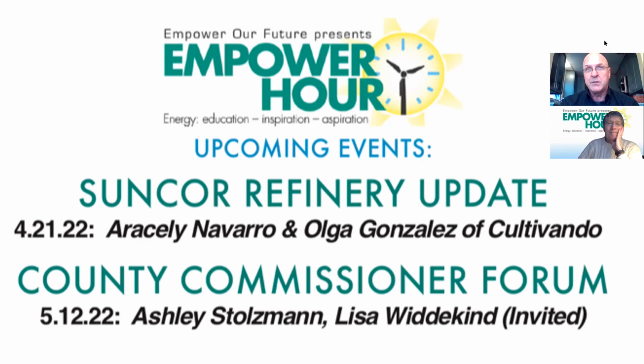They pull about 80% of the power out of their supercapacitors every day, doing peak shaving as the machines go off and on. And then at night, when everybody's gone home, they recharge those. They do mitigate it to some degree also with some solar that they put on the building, but that's how the supercapacitors are used. And that reduces their overall cost because it lowers that peak. Once the peak's lower, the kilowatts that are multiplied times $1.5 go down.